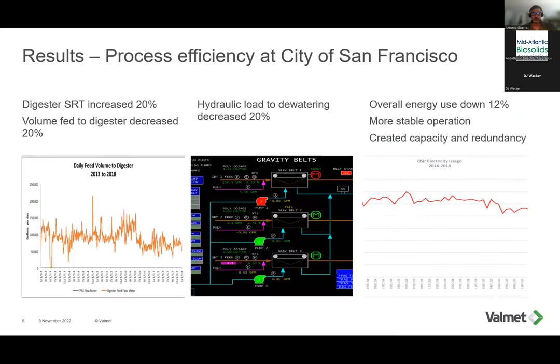So some of the results that they shared, this was based on a paper that was presented at the WEF conference a few years back, but just by enabling and improving controls based on those measurements, basically you can see some of the variables that they were able to reduce and cost savings. For example, volume fed at the digester decreased by 20%. So again, it's just based on having thicker sludge coming into the digesting process as opposed to wet sludge, you create volume.